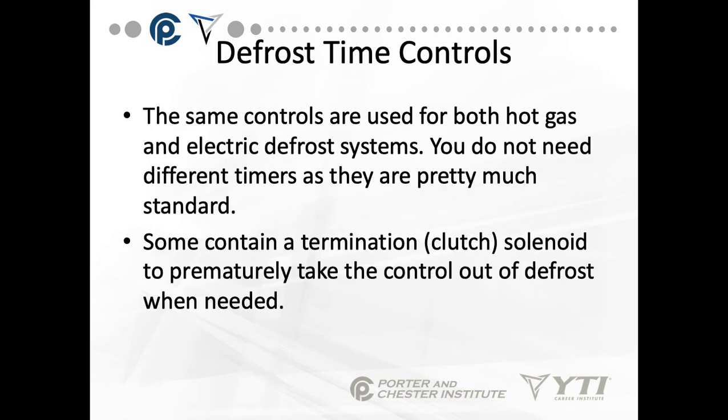The same controls are used for both hot gas and electric defrost systems. You do not need different timers, as they're pretty much standard. Some do contain a termination solenoid that prematurely takes the control out of defrost when needed — it energizes a solenoid that actually pushes the defrost timer back into cooling mode once the ice is off the coil.